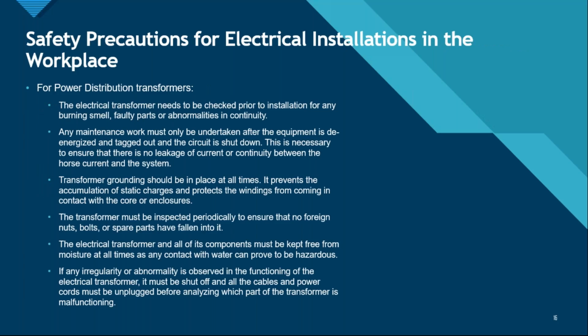Then let's move on to the safety precautions for electrical installations in the workplace. Right, for power distribution transformers, the electrical transformer needs to be checked prior to installation for any burning smell, faulty parts, or abnormalities in continuity. Any maintenance work must only be undertaken after the equipment is de-energized and tagged out and the circuit is shut down, right? This is necessary to ensure that there is no leakage of current or continuity between the hot current and the system.